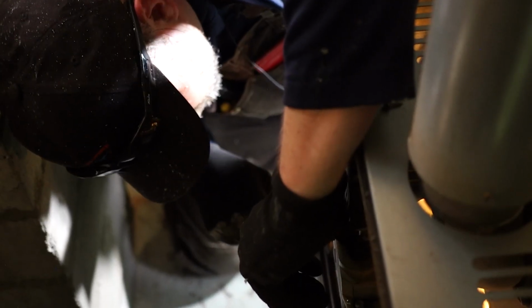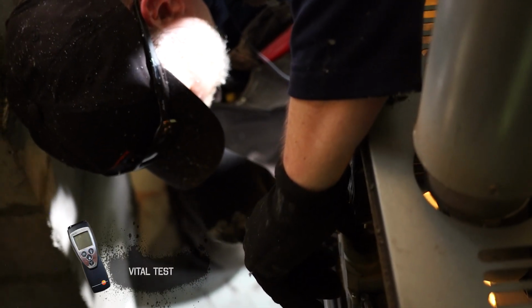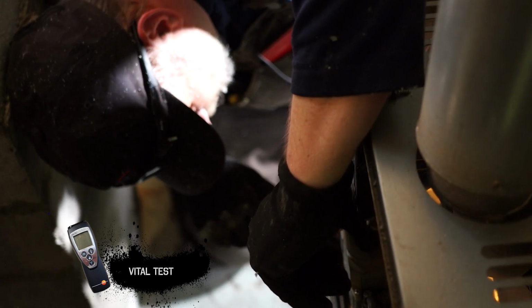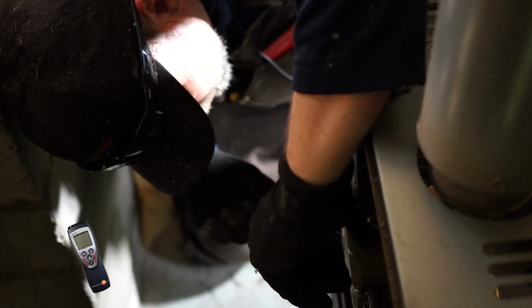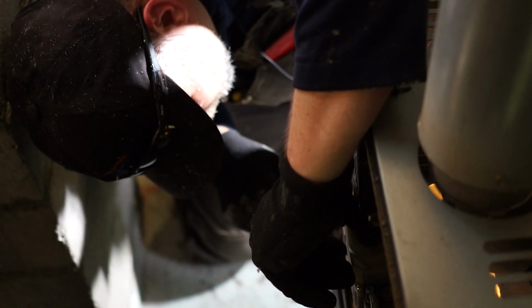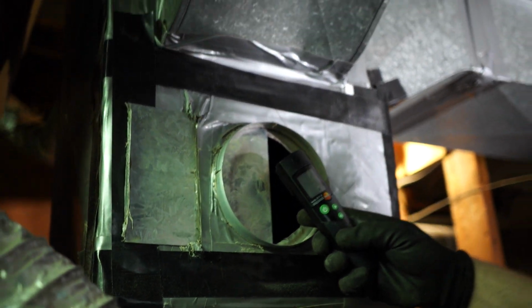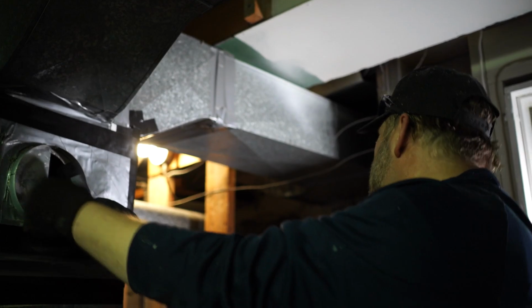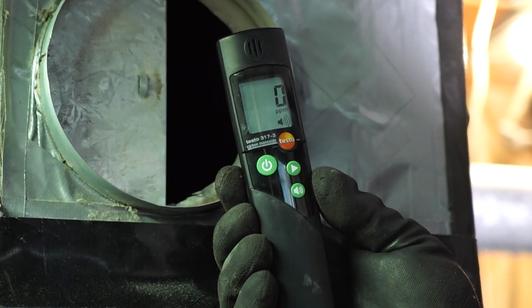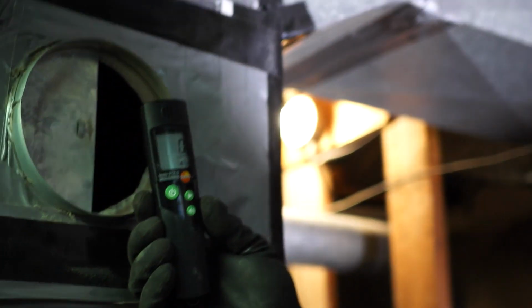Next thing we're going to check for is carbon monoxide leaks. This can be caused by a plugged heat exchanger or a cracked heat exchanger. I'm going to check the airstream with my Testo carbon monoxide detector. I've removed the humidifier bypass, which is allowing supply air to come out. As you can see, we have 0 parts per million carbon monoxide.